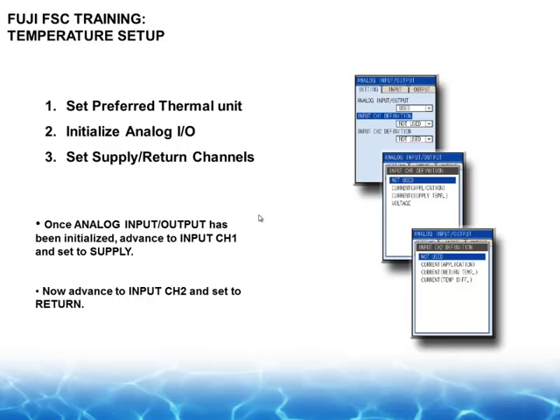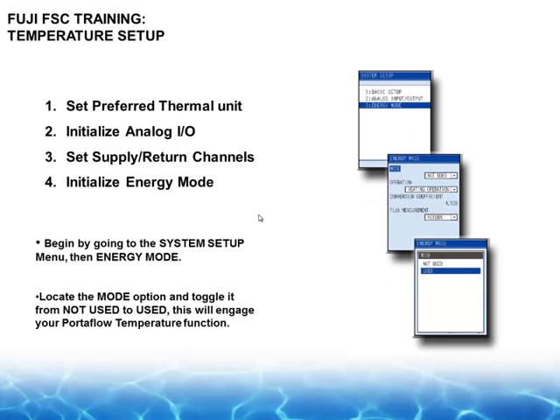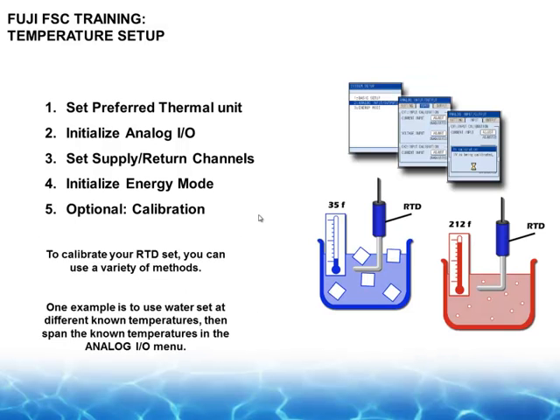If you've got bad BTU calculations, the first thing to do is go back and analyze all the sub data. So you have flow and the temperatures, and it'll be nicely identified here. And the same thing with input channel 2, set that up for your return. Then you go to the System Setup menu and then to the Energy mode. You locate Mode option and toggle it from not used to used, and this will engage your Portaflow temperature function.